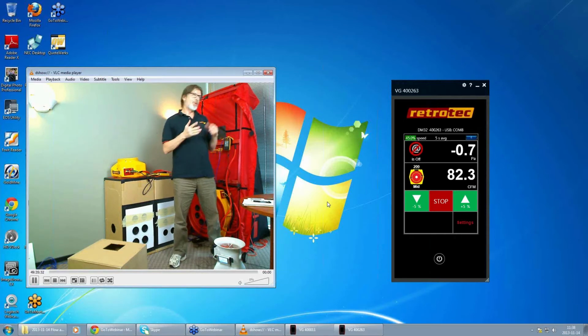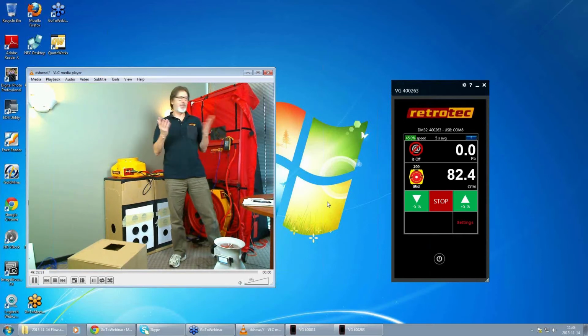So for those of you who don't know what square root is, square root of 25, for example, is 5. 5 times 5 is 25. So the square root of 25 is 5. The square root of 49 is 7. So if you're doing it at 50 pascals, the square root of 50 is about 7.1, times the area, times 1.07 equals the flow.